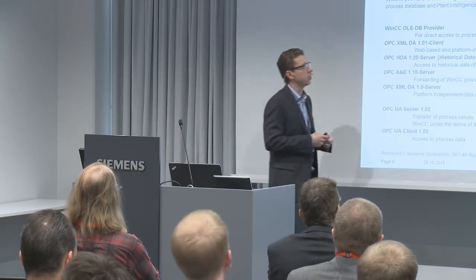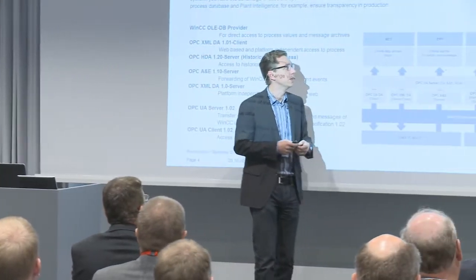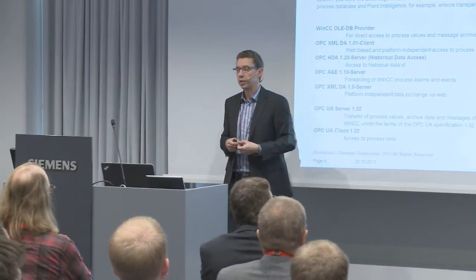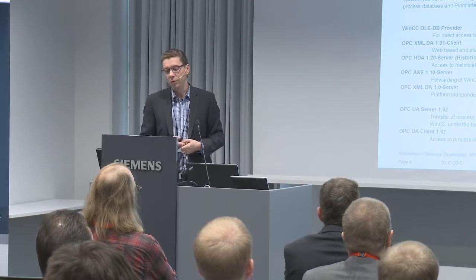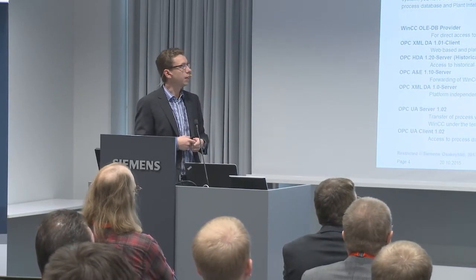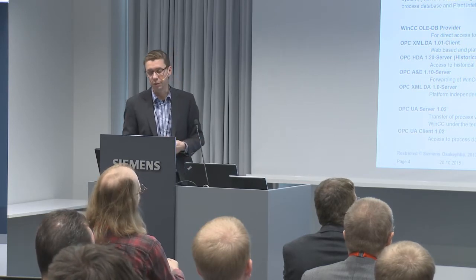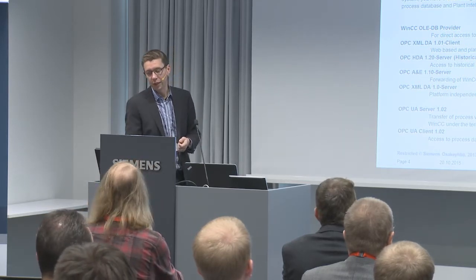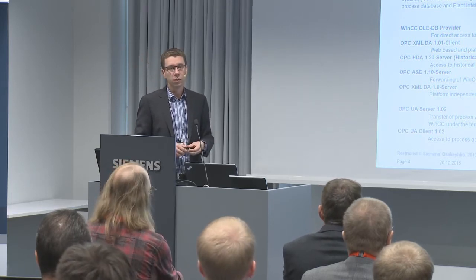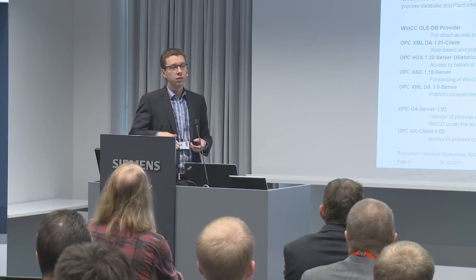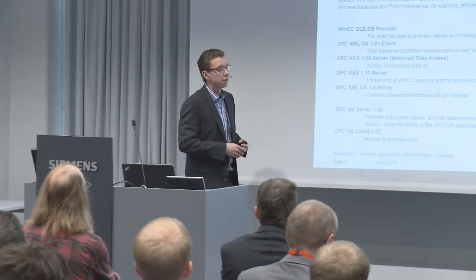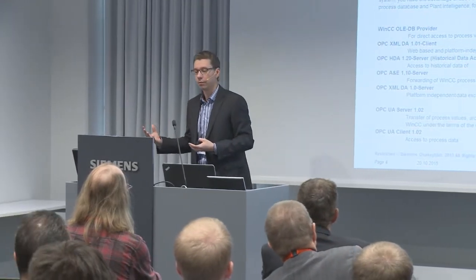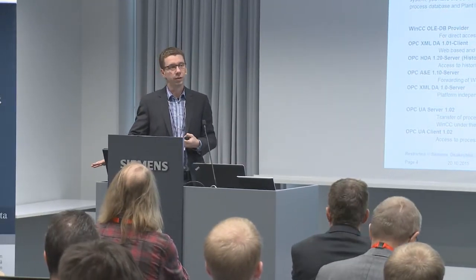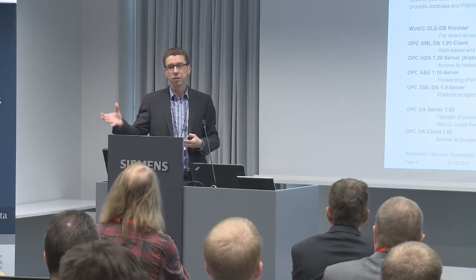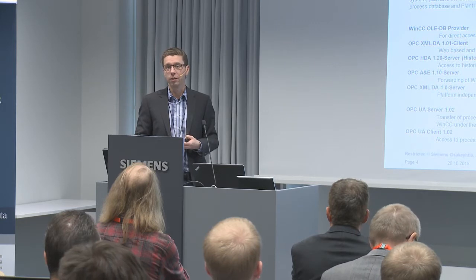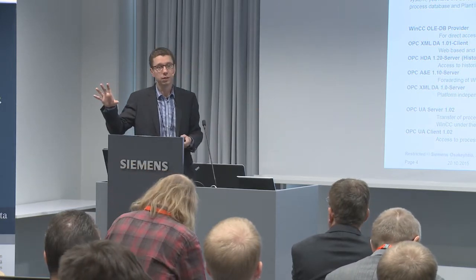So we can have WinCC as an OPC UA client to another system, or it can provide content as an OPC UA server. The main usages are, for example, connectivity to MES, ERP, or third-party applications created with normal programming languages nowadays. The connectivity from WinCC towards the PLC level is typically done in the Siemens world with our S7 protocol, so that you have connectivity to the PLC level via the WinCC SCADA software, getting data from the plant floor level via the SCADA system, offering a gateway solution straight away without needing a separate connector box.